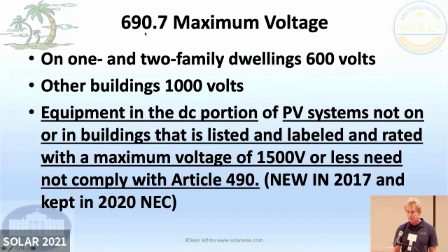So here we have 690.7. That's for voltage in the NEC. Here's the speed limit or the voltage limit. 600 volts for 1 and 2 family dwellings, 1,000 volts for other buildings, and you could put a 1,500 volt inverter in your backyard. But usually, I don't know anybody who has. For utility scale, it's almost always going to be 1,500 volts. And that's your maximum system voltage. So you put all your PV modules together in series and you do the calculations for the coldest day of the year and when it's turned off, and you can't go over 1,500 volts.